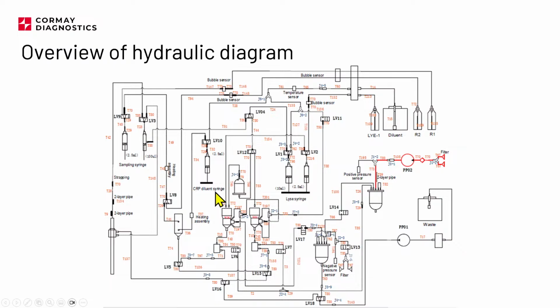The next thing is the CRP diluent syringe. So it splits like here, one valve, 2.5 milliliter diluent syringe. It goes through the heating assembly, and it's also going into the CRP assembly here. I mean the CRP chamber basically. You may notice that there is no air bubble supply. And yeah, this is true because if I remember correctly, the analyzer is mixing everything with a diluent syringe. I think it's going up and down a few times.